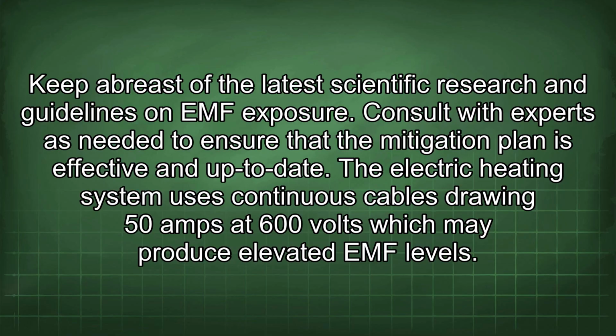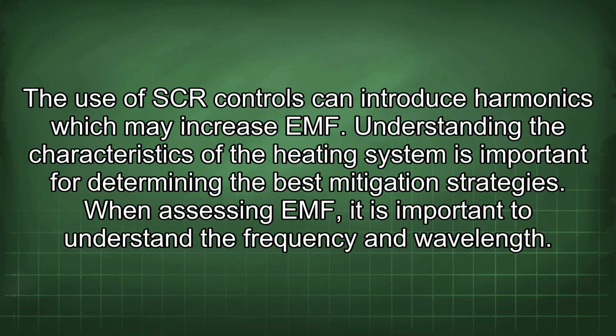The electric heating system uses continuous cables drawing 50 amps at 600 volts, which may produce elevated EMF levels. The use of SCR controls can introduce harmonics which may increase EMF. Understanding the characteristics of the heating system is important for determining the best mitigation strategies.